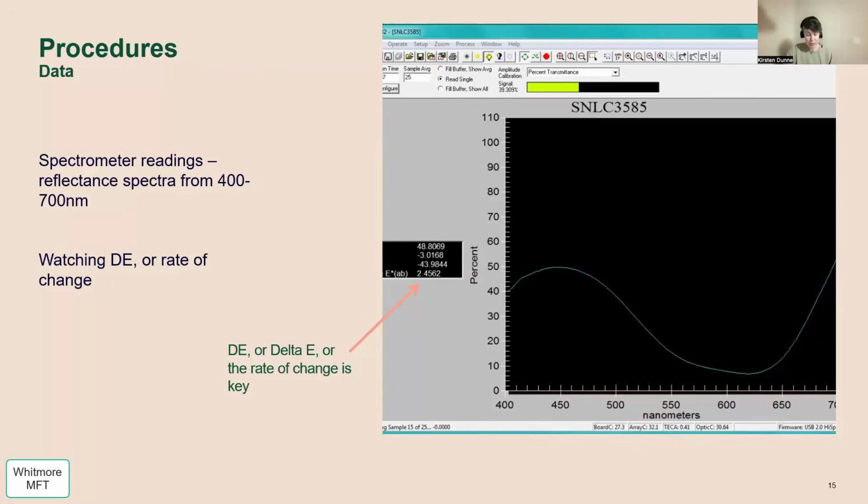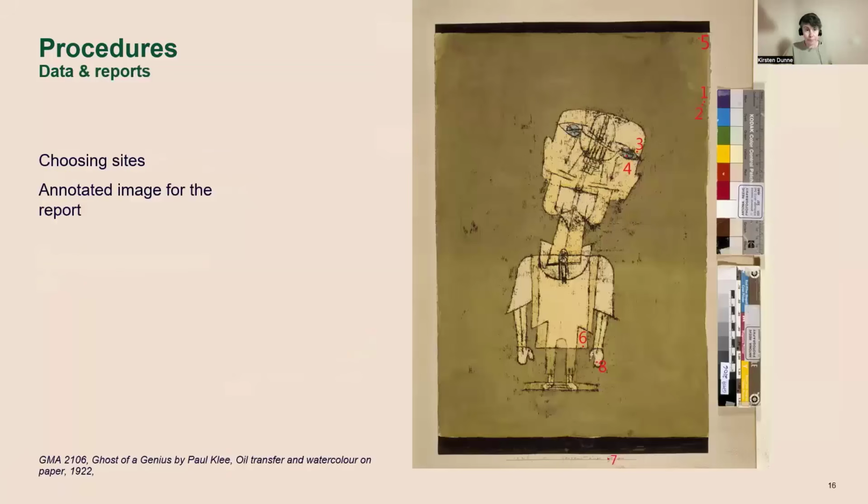10 minutes is sort of a nice balance. It's a good amount of time to get data, a decent amount of information to support risk-based decisions. But it's also time efficient in terms of running multiple tests per day. Like I mentioned, when I'm doing a fade test run, I'm often doing data assessment on the previous run and starting to write the report. So overall, it's quite a time efficient process.